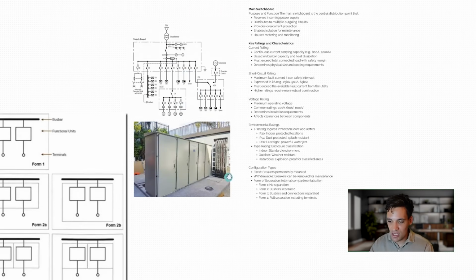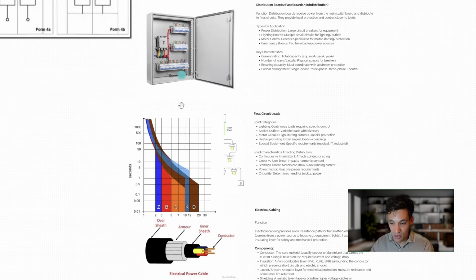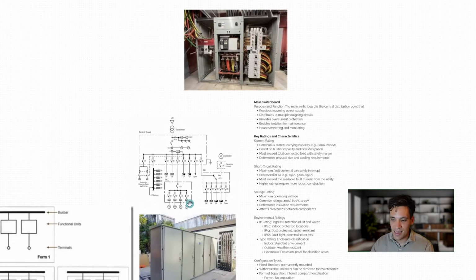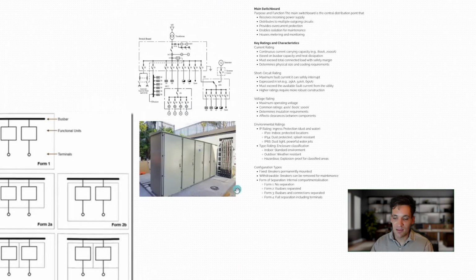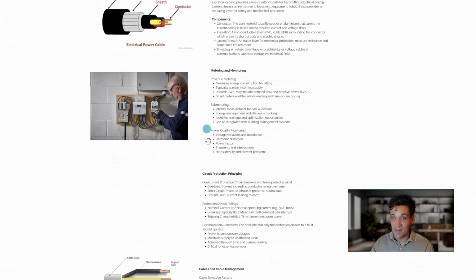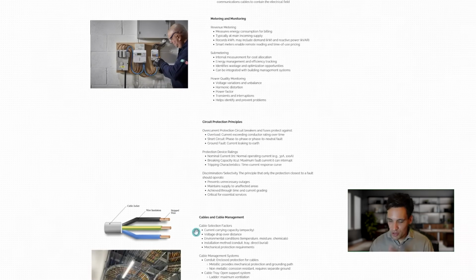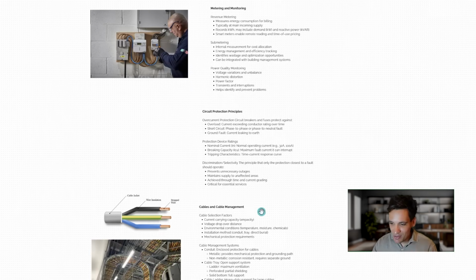So with discrimination and choosing the correct time current curves for our circuit breakers, we want to ensure that this breaker trips before that breaker, which is all about circuit breaker sizing and discrimination. What you're going to begin to see when we talk about circuit breaker sizings and certain circuit breakers only allow certain cable sizes is that all these components start to merge together, where the size of the main switchboard impacts what circuit breakers you choose, which impacts what cables you choose. But then you choose a bigger main switchboard, it only fits in a certain location. So suddenly all the devices it connects to are further away, which means you get more voltage drop, which means you change the cable. It becomes a bit of a balancing act.